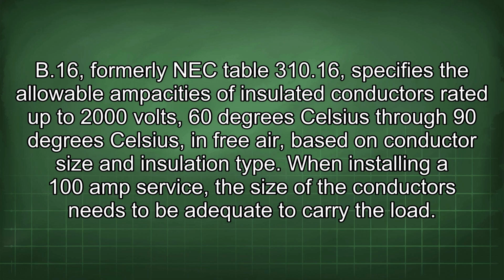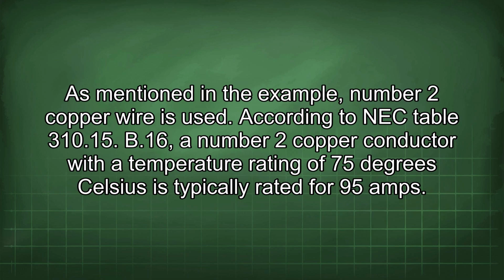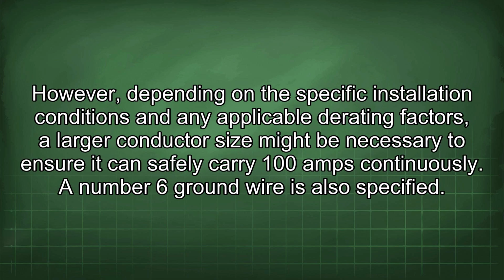When installing a 100 amp service, the size of the conductors needs to be adequate to carry the load. As mentioned in the example, number 2 copper wire is used. According to NEC Table 310.15(B)(16), a number 2 copper conductor with a temperature rating of 75 degrees Celsius is typically rated for 95 amps. However, depending on the specific installation conditions and any applicable derating factors, a larger conductor size might be necessary to ensure it can safely carry 100 amps continuously.